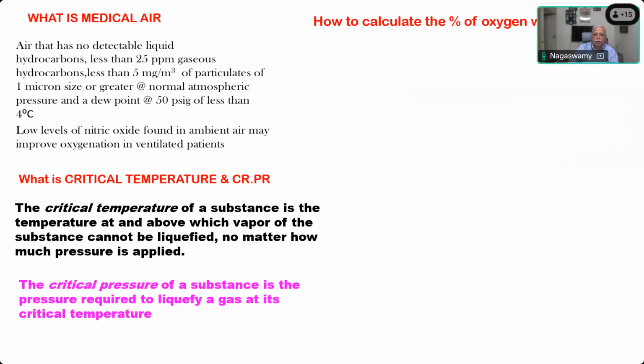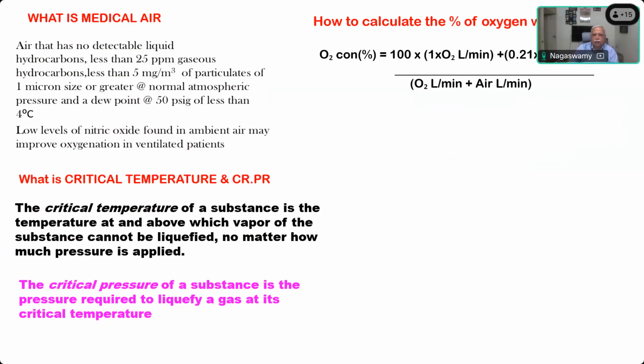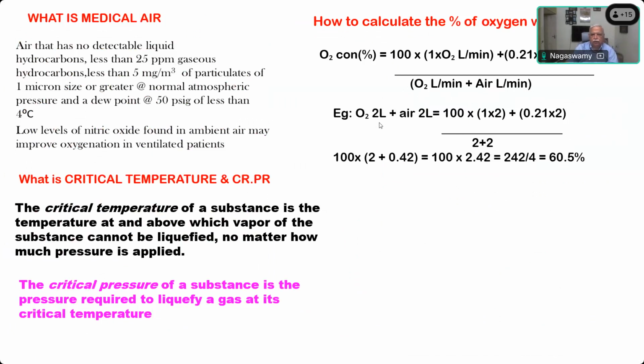Shall we see the formula? Oxygen concentration is equal to 100 into 1 into oxygen in liters per minute plus 0.21 into air in liters per minute, divided by the total of the oxygen and air combination. For example, suppose you use 2 liters of oxygen and 2 liters of air. Now this is 100 multiplied by, this is 100% oxygen, and you are using 2 liters.